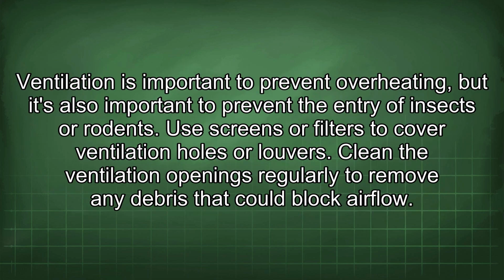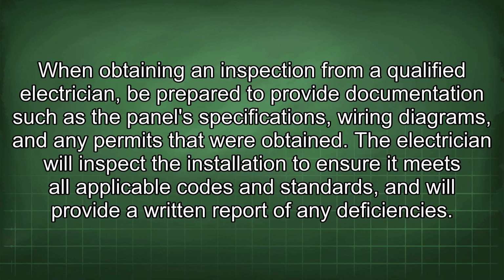Ventilation is important to prevent overheating, but it's also important to prevent the entry of insects or rodents. Use screens or filters to cover ventilation holes or louvers. Clean the ventilation openings regularly to remove any debris that could block airflow. When obtaining an inspection from a qualified electrician, be prepared to provide documentation such as the panel's specifications, wiring diagrams, and any permits that were obtained.